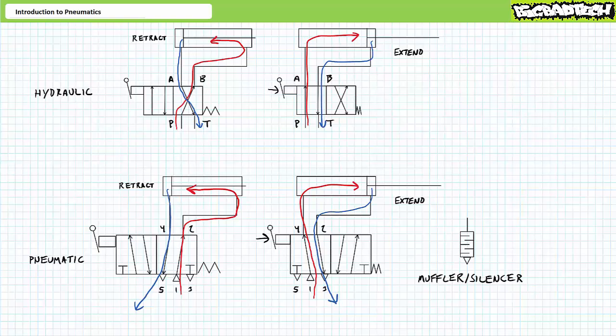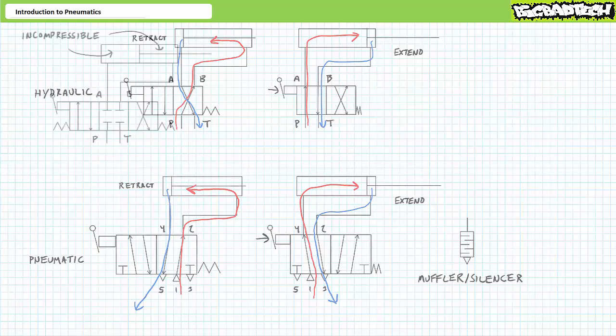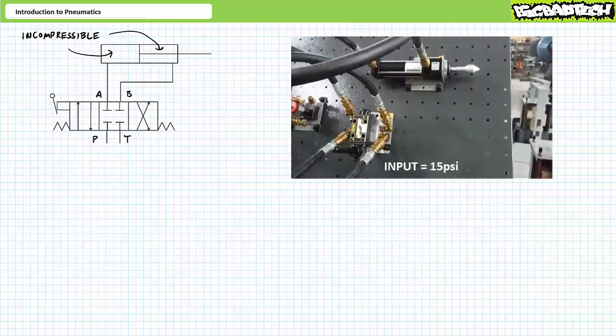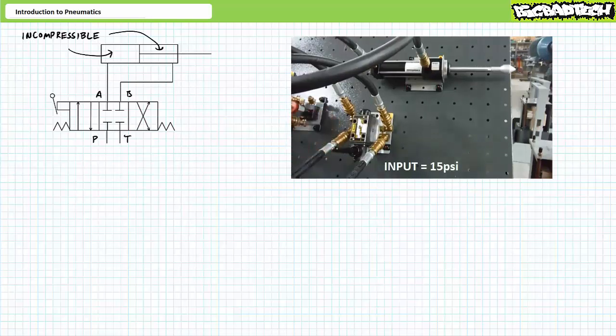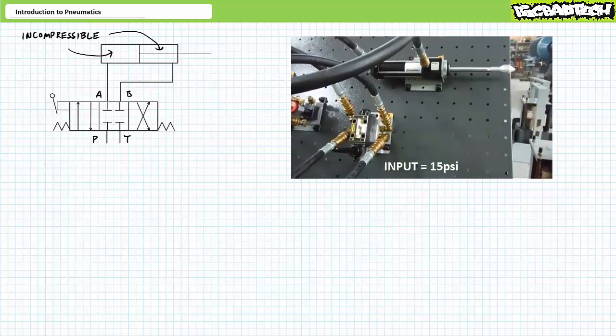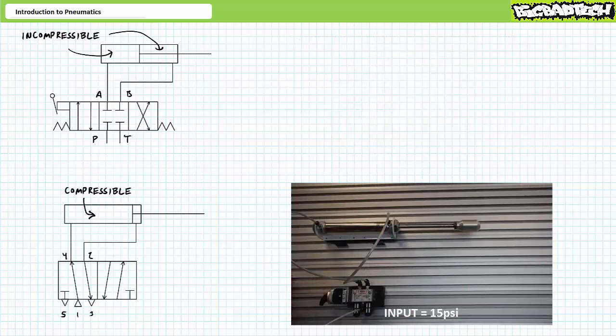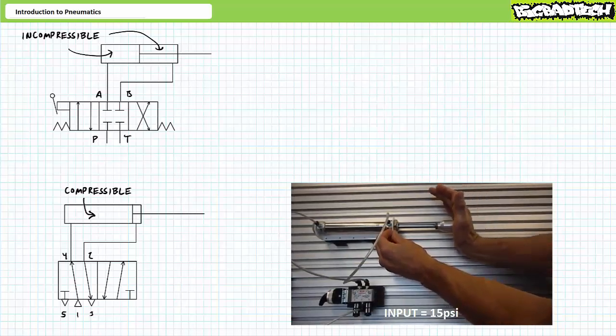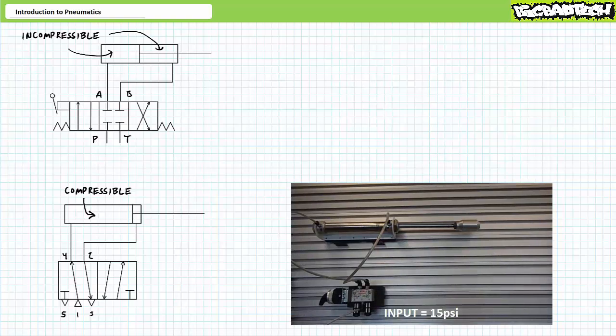Important differences do exist, largely due to oil's incompressibility and air's compressibility. Consider a double-acting hydraulic cylinder with a three-position valve, spring-centered in a closed-center position. The oil on the cap end and the rod end are incompressible — for all intents and purposes, you could swap out this oil and fill it with rock, steel, or solid concrete. Oil is incompressible and that cylinder will remain rigid, locked, and fully extended. Not so much in a pneumatic system. Consider a pneumatic cylinder at full extension — the air in the cap end is compressible. If the extended rod encountered sufficient resistance, there'd be a little give to it because of air's inherent spongy compressible nature. This would be great if you wanted to lift or push something but still absorb shocks. Because of air's compressible nature, pneumatics might have a little spongy give to them — depending upon application, this might or might not be a desirable feature.